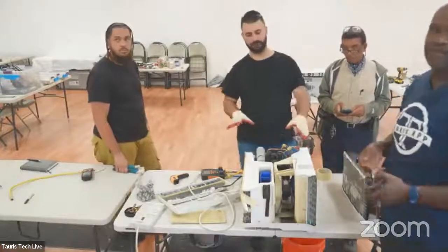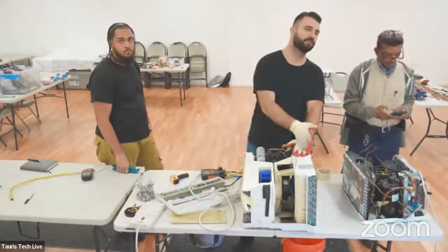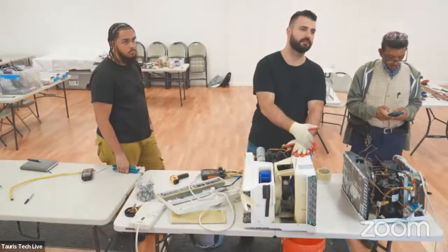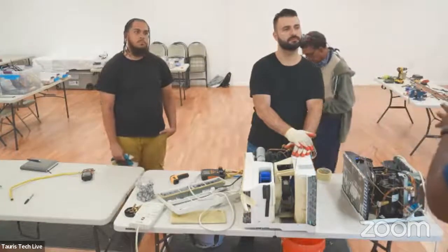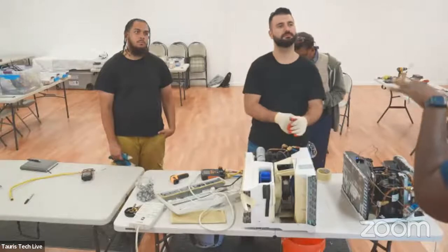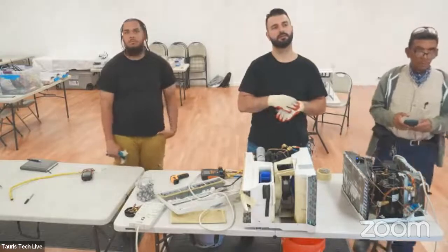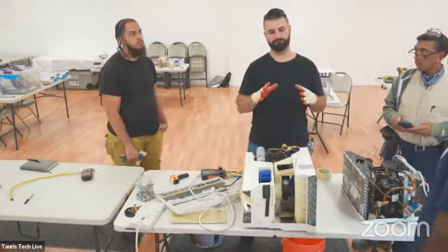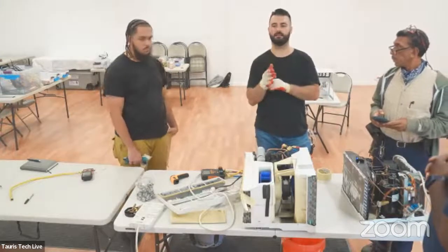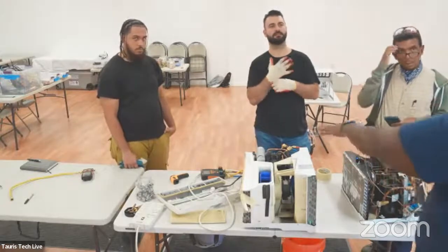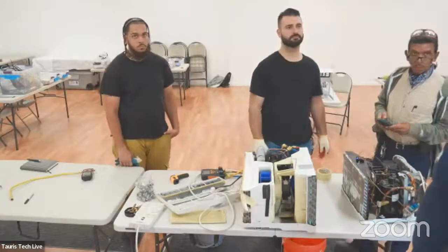And so they switch refrigerants, like from R22, if I'm not mistaken, to 407, right? We're just at a building where they changed an R22 chiller to 407C because the pressures are close. But when you do that, you have to change the oil. You have to really flush it because they're completely different types of refrigerants. They pick 407 just because the pressure numbers are close. If you put 410A in there, the pressure is way higher, so it would probably kill the compressor.